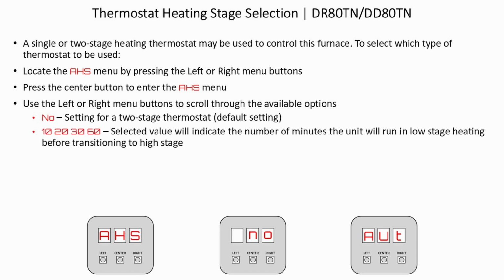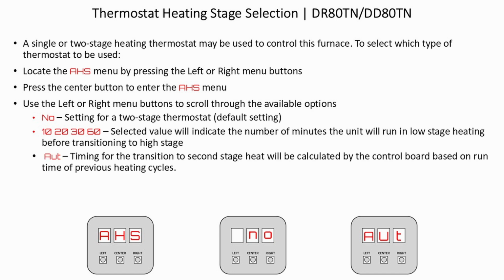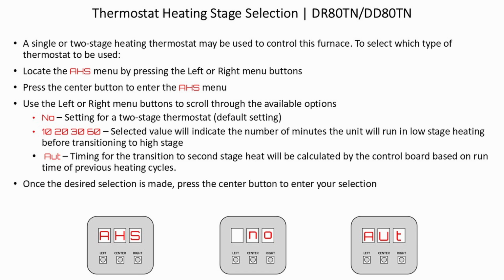10, 20, 30, 60. Selected values will indicate the number of minutes the unit will run in low stage before transitioning to high stage. AUT: the timing for the transition to second stage will be calculated by the control board based on run time of previous heating cycles. Once the desired selection is made, press the center button to enter your selection.